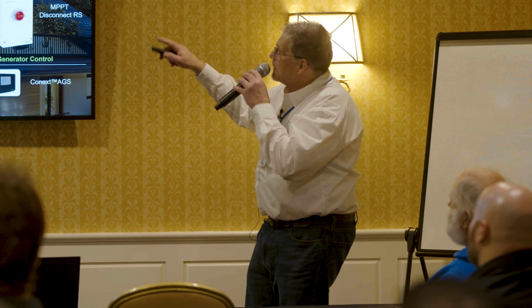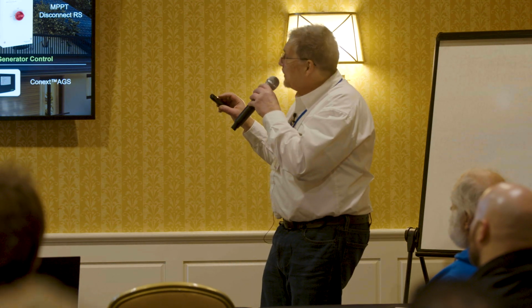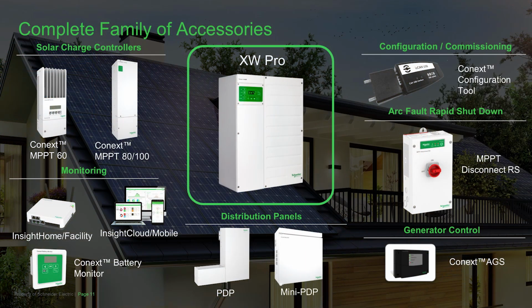All right, so I just wanted to cover the complete family of accessories for those of you who are not familiar with the XW Pro platform. So we have actually 3 models of solar charge controllers. We have MPPT 60, which is a 150 volt DC max on the PV side. It provides 60 amps to the battery with an appropriately sized array. We have MPPT 80 and MPPT 100. Those are our high voltage charge controllers. They operate up to 600 volts on the PV side.